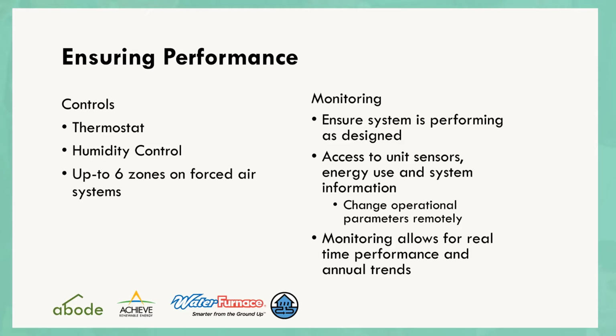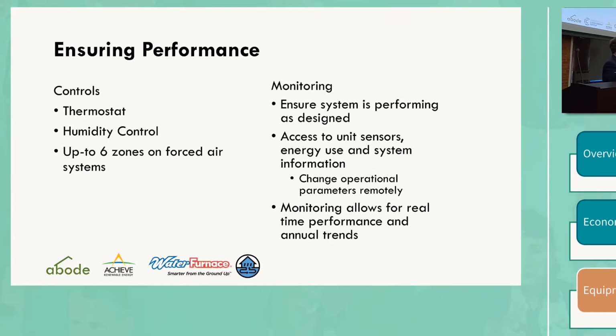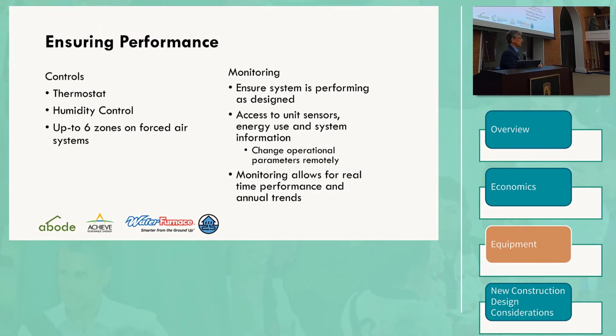The controls for a ground source heat pump system can be quite sophisticated because one ground source heat pump, especially the WaterFurnace equipment, can modulate its output in a way that a conventional system can't. So one ground source heat pump can support multiple temperature zones. In the case of the variable speed WaterFurnace equipment, up to 6 temperature zones off one machine, providing that you can make all the ducting runs to also support those zones, which normally you can in new construction.